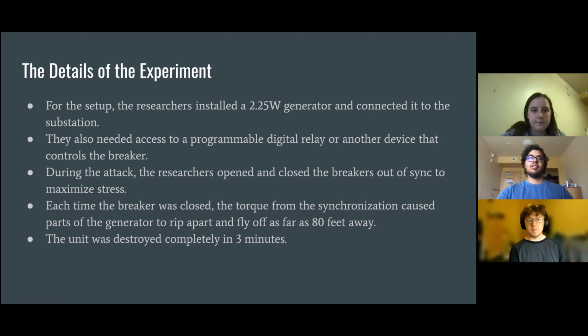This means the turbine that spins inside the generator was made to stop and restart when it was out of sync with the rest of the things it was connected to, making it jump up and down erratically, smoke, and all that kind of stuff. Each time the breaker was closed, the torque from the synchronization caused parts of the generator to rip apart and fly away as far as 80 feet. That's really, really far away, and we can see that in the video we'll show you coming up.